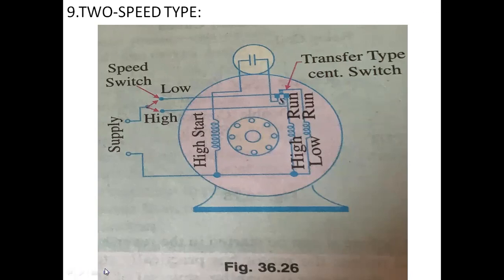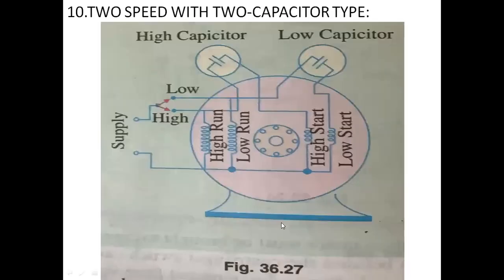Last type: two-speed with two capacitor type. Two capacitors are used with two speeds. This motor has two running windings — high and low — two starting windings — high and low — and two capacitors. One capacitor is used for high-speed operation and the other for low-speed operation. A double centrifugal switch is employed for cutting out the starting winding after starting.